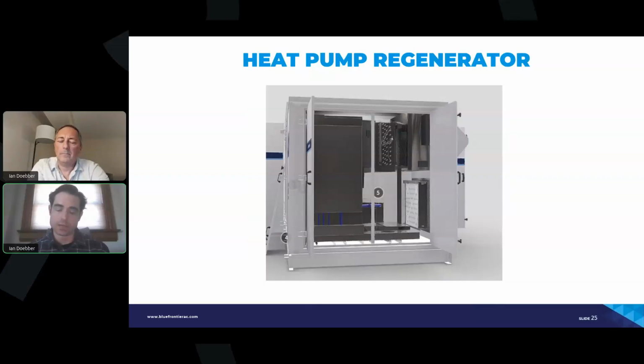The desiccant comes in here, and we heat it with the hot refrigerant leaving a scroll compressor. Then the hot desiccant sees hot air that we're also heating. The moisture is transferred from the desiccant to the air, and then we simply dump that air outside. Because we run the unit as a heat pump in heating mode during the cooling season, we become more efficient the hotter it is outside. We monitor the regenerator efficiency in real time through our IoT system, and we see about a 15 to 20% increase in efficiency as the temperature goes from around 80 degrees to the low to mid 90s. So it's a dramatic improvement in the efficiency of the system at hotter temperatures.